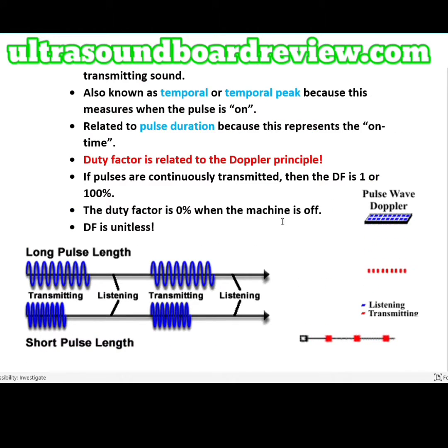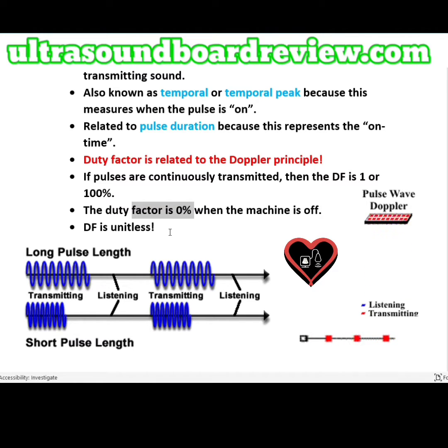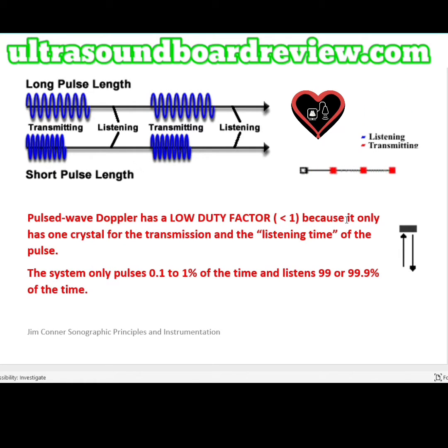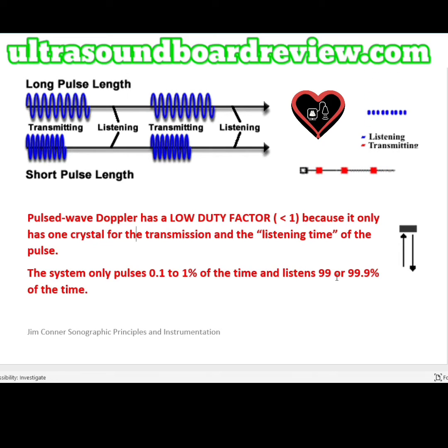When the machine is off, your duty factor is zero percent. Keep in mind that duty factor is a unitless number. Pulse wave Doppler has a low duty factor of less than one because it only has one crystal for both transmission and listening. The system only pulses 0.1 or 1% of the time and listens 99 to 99.9% of the time.